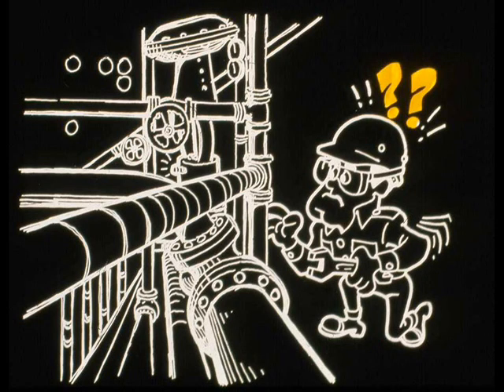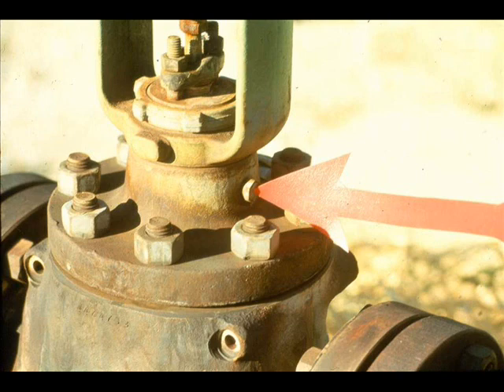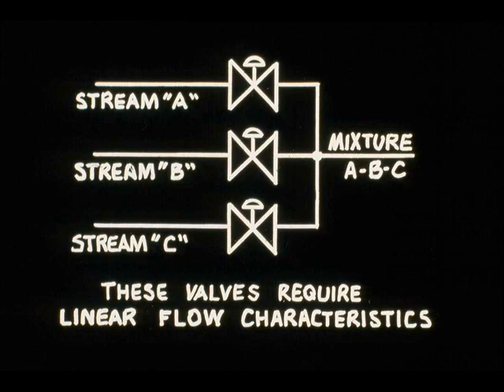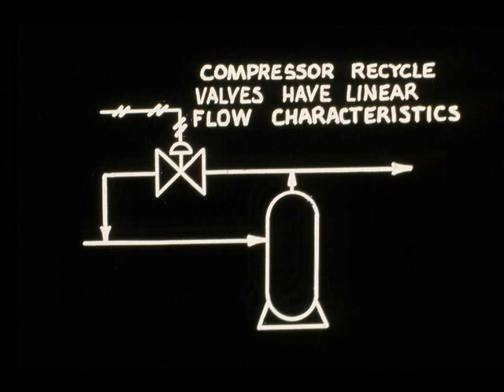The lubricator should be installed where it can be reached. The valve packing box shall be threaded and fitted with a 1/4-inch NPS steel plug if a lubricator is not supplied. Care should be taken that fins or extensions are not insulated, otherwise it would defeat the purpose of a finned extension. Two-way control valves shall have equal percentage characteristics, except valves used in combining or diverting service shall have linear characteristics. Characterized positioners may be used to meet this requirement. Gas compressor recycle control valves shall have linear characteristics.